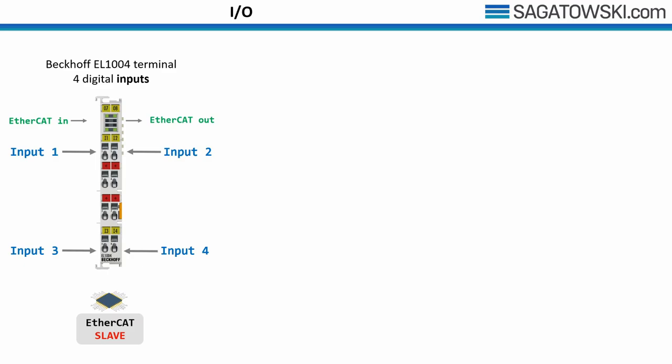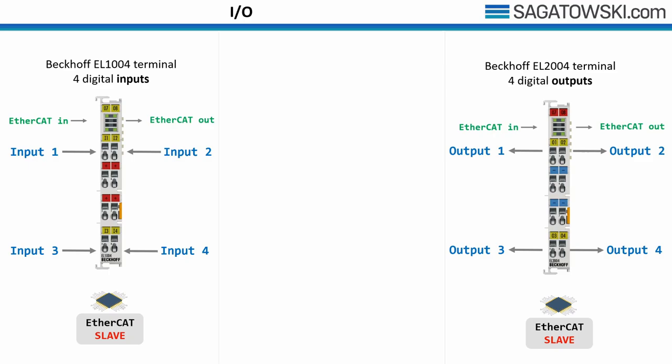There are also terminals to do the opposite — when you want to actuate something with a 24V output. The equivalent is the EL2004 terminal, which houses 4 digital outputs. Beckhoff are not the only ones manufacturing fieldbus devices with EtherCAT capability. One of my favorite devices is manufactured by the company IFM. This supports 4 channels of IO-Link, which is a bidirectional point-to-point industrial communication standard for connecting digital sensors or actuators based on a serial protocol, allowing it to exchange a vast set of data. These are just a few examples — there are thousands of other fieldbus devices out in the wild.